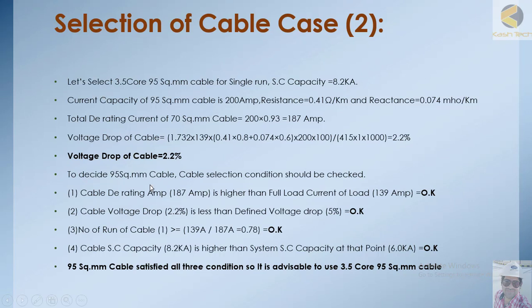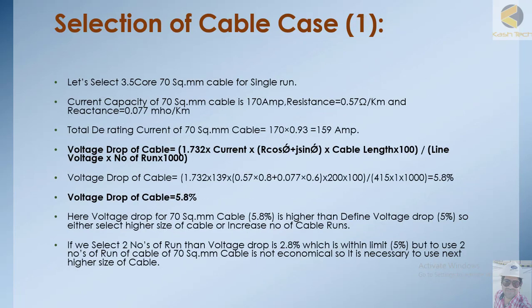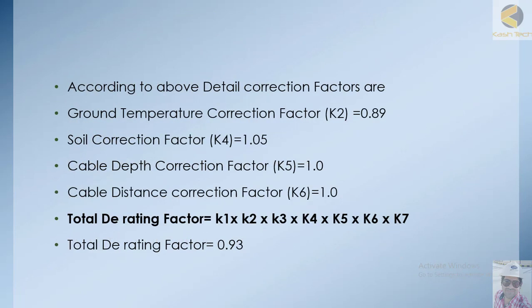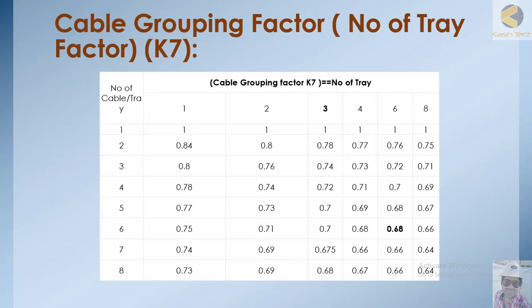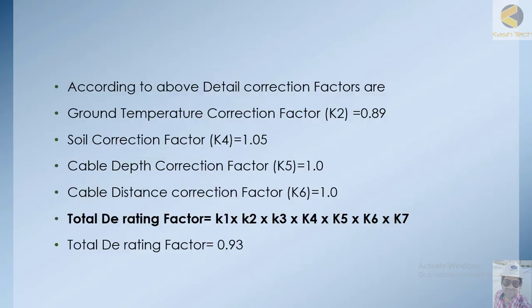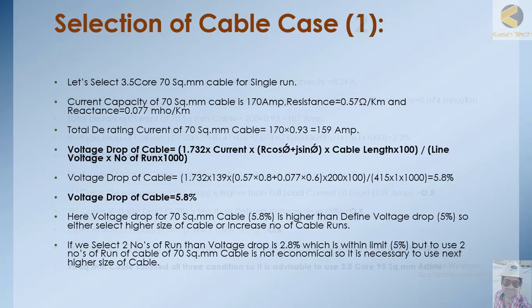Therefore, it is advisable to use a 3.5 core 95 square mm cable. This concludes the example for cable size calculations. I hope you enjoyed this section — thank you very much.